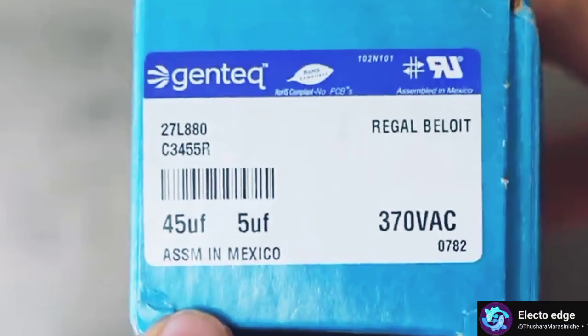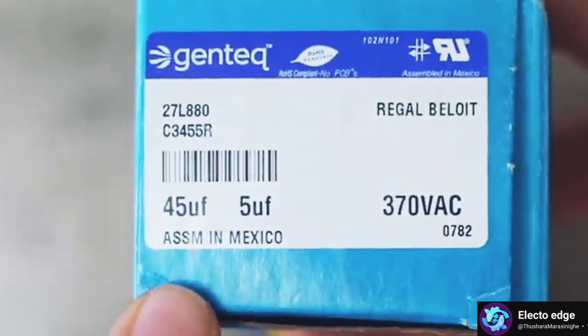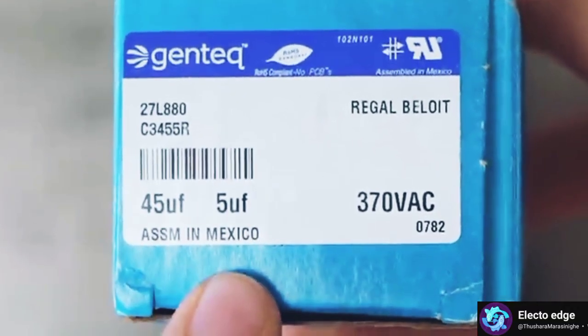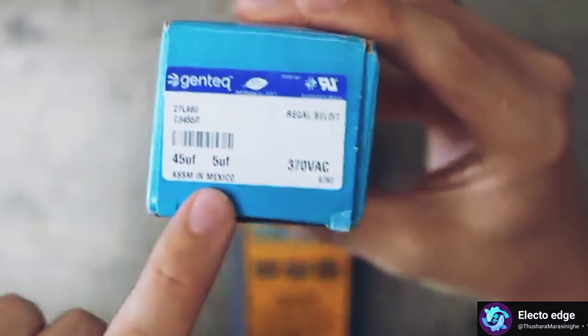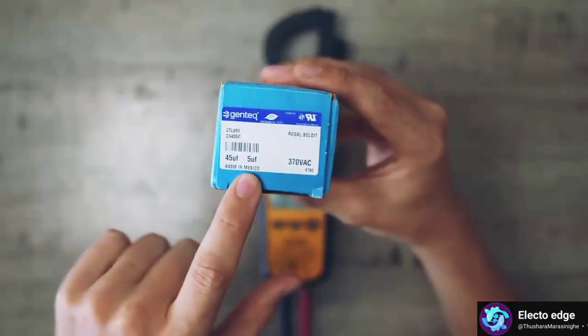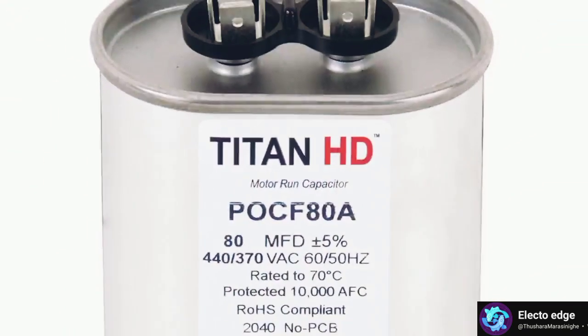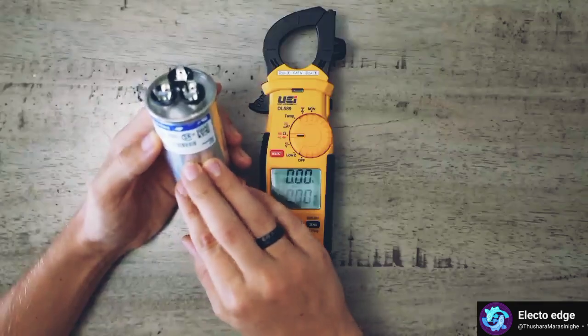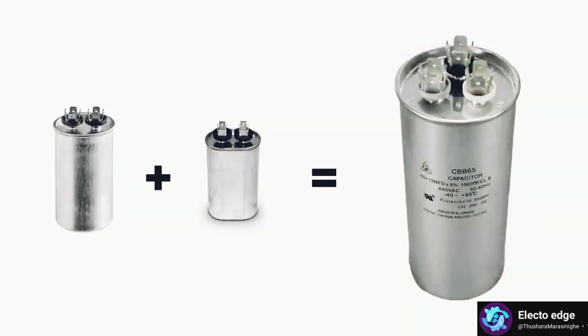So right here I have a dual capacitor, which is rated 45 microfarads and 5 microfarads. And sometimes instead of this backwards letter U, you're going to have the letter M. So it'll be MFD, which is the same exact thing as UF and stands for microfarad. This right here is a dual capacitor, which means there's 2 capacitors in one. So let's go ahead and check both of them.